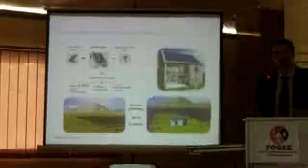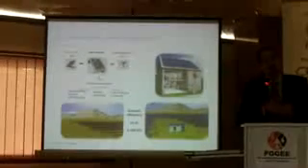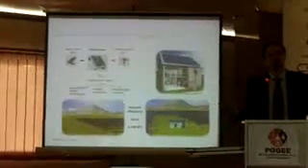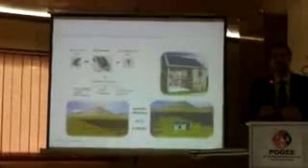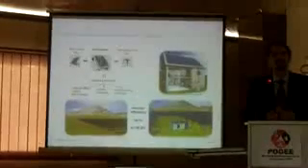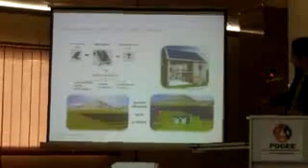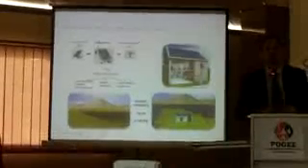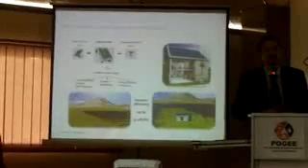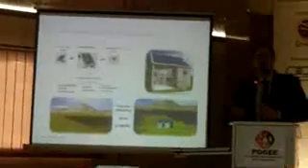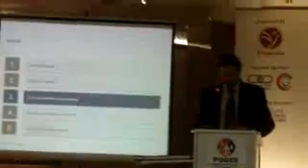If you have a central inverter, you would have a lot of strings and solar panels connected to one inverter. You would need additional DC-based monitoring in the field, represented by these boxes here, to see what's really going on in the strings, and if there's an error, to locate it. And then also you evacuate it and have a step up to the medium voltage level.